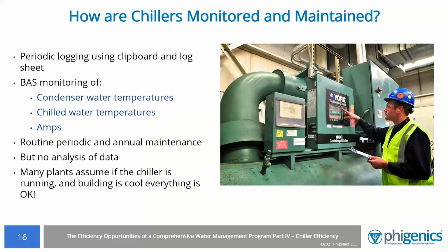So, even with brand new chillers that collect reams of continuous data that is recorded somewhere in your building automation system or the chiller itself, we still find facilities maintenance personnel recording some of it on a clipboard. In addition, every chiller has alerts or alarms to warn of serious problems, and everyone performs periodic maintenance. But in the majority of facilities we see, there is no analysis of the data collected that shows you where you are on the continuum between operating your chillers at design efficiency or operating your chillers at the ragged edge of efficiency or even failure.